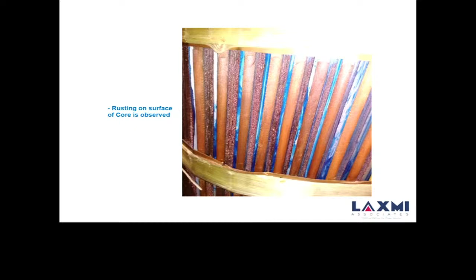So like one measurement here, what you see is that everything is good, tan delta is good, moisture is good, but the conductivity is high. It's possible because conductivity has nothing to do with your moisture content. Conductivity is a different dielectric parameter, moisture is a different dielectric parameter. But here the clear indication is there, okay, your conductivity is high, but your moisture is in control.